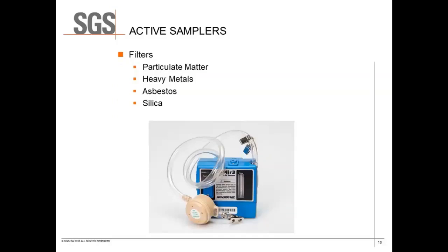For active sampling with filters, you need a fully charged and calibrated pump. You hook the media up to the sample pump, turn it on, and draw air through the filter media, collecting the contaminant onto the filter — you're pulling the whole air sample but only collecting the contaminant onto the filter or sample media. Filters are typically used for particulate matter, heavy metals, asbestos, and silica.